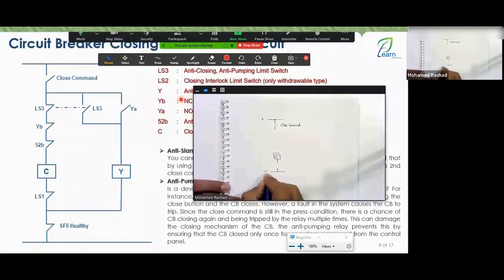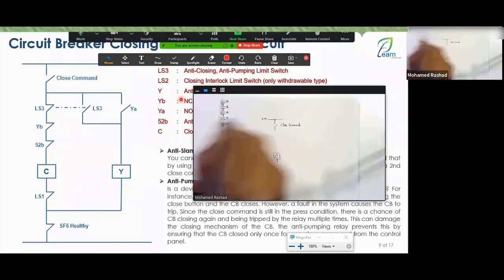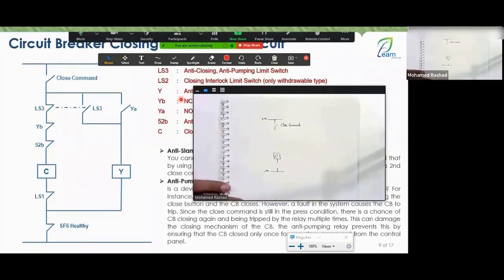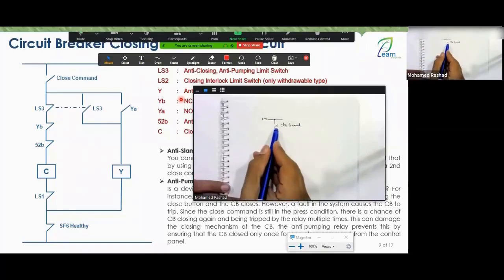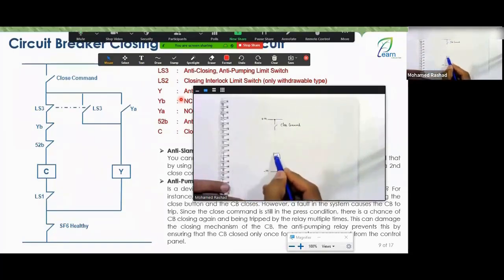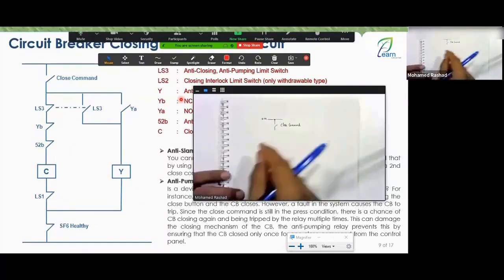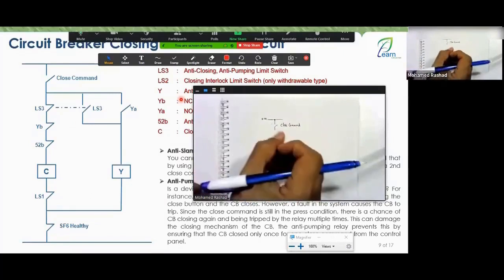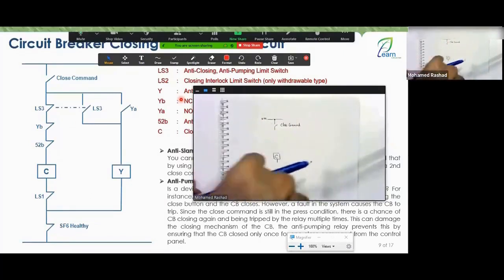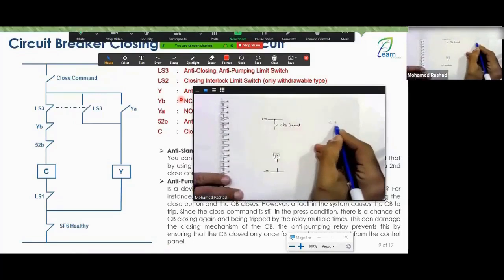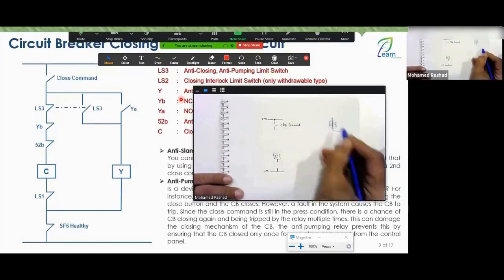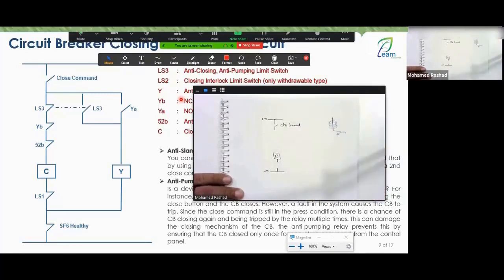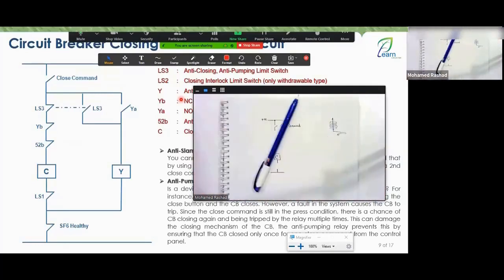Here you have the negative and here you have the positive. Is that good? I said to him, great. He said, all right, engineer, if you give me a close, the DC will reach the closing coil with the positive from above and the negative from below. It will act like what we saw in the video, starting to release and pull your coil. And there was a column here. It pulled this column upwards, releasing the mechanism, so the mechanism started to move, and it closed the circuit breaker.